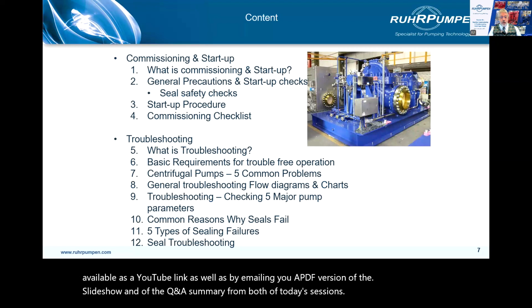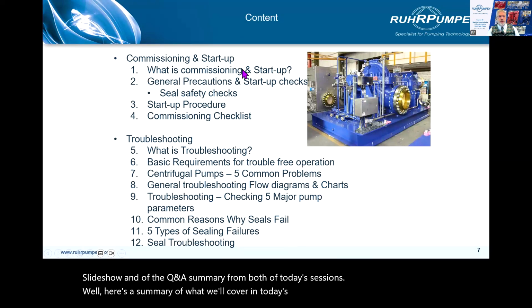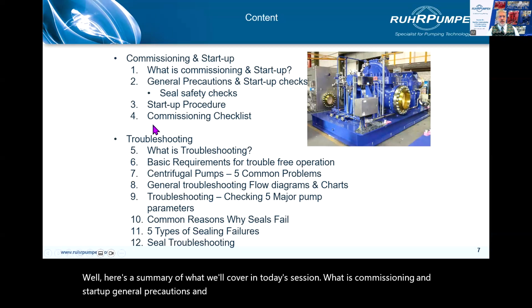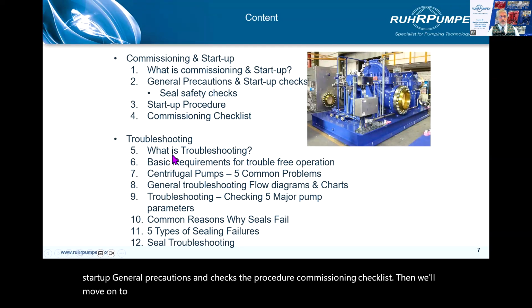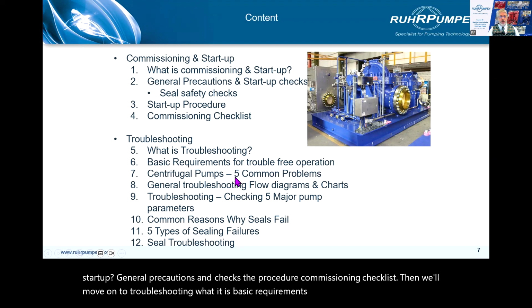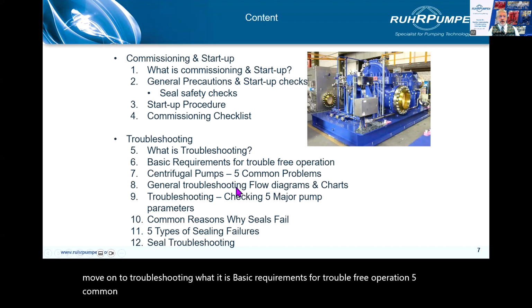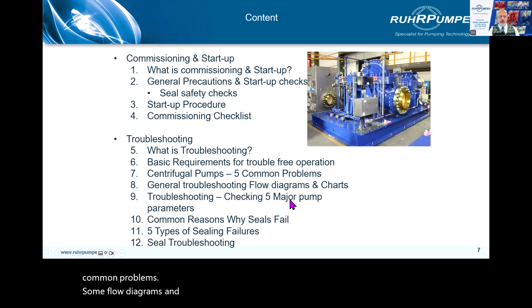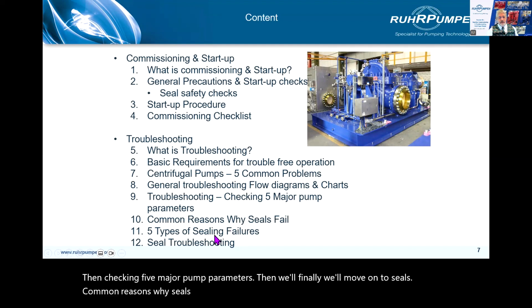Well, here's a summary of what we'll cover in today's session. What is commissioning and startup? General precautions and checks, the procedure, commissioning checklist. Then we'll move on to troubleshooting, what it is, basic requirements for trouble-free operation, 5 common problems, some flow diagrams and charts, then checking 5 major pump parameters. Then we'll move on to seals, common reasons why seals fail, the types of failures, and some troubleshooting on seals.